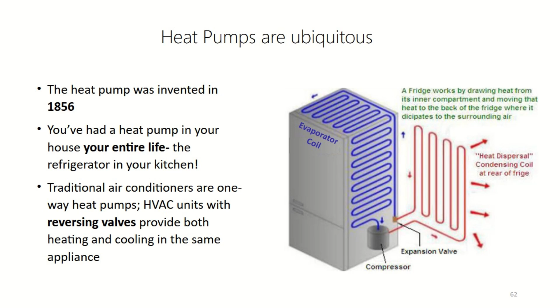The difference between a traditional air conditioner and a heat pump is really just 2 components: a reversing valve and a defrost controller. In heating mode, if humidity and outdoor temperature are right, you might get frost on the outdoor coil. So there needs to be a means of controlling that, whether a resistance element or running the heat pump in reverse to blow hot air over it, getting hot refrigerant through to get rid of the frost. Otherwise, it's almost the same as the air conditioner you have now, it just works in both directions, so you get 2 end uses out of the same appliance.